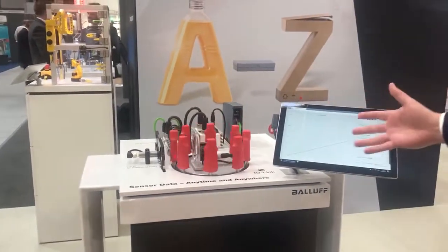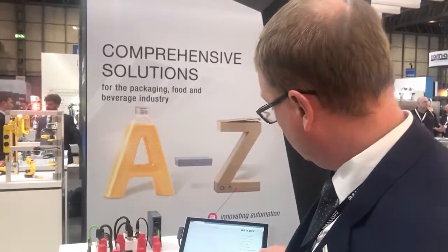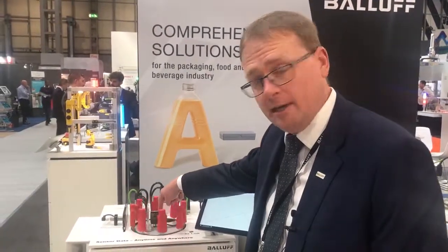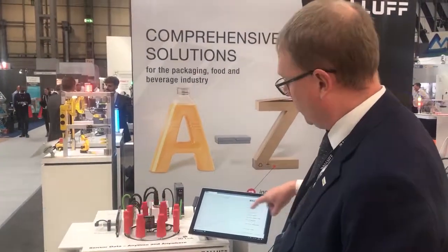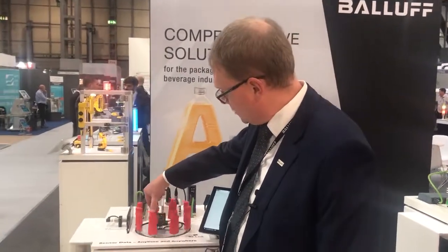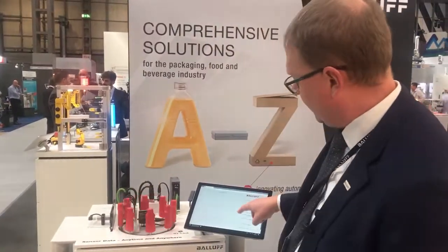At the minute, on our little visualization HMI display, it's in diffuse sensor mode, and we can get all the lifetime data out of the sensor. There's a temperature monitor inside there. We can work out the strength of the LED emitter coming out of it, so we can get real lifetime diagnostics from the sensor. This little slide on the front here is imitating a dirty lens. So when I move it over, you can see the gain on the HMI moves up, indicating that we've got a dirty lens on there.